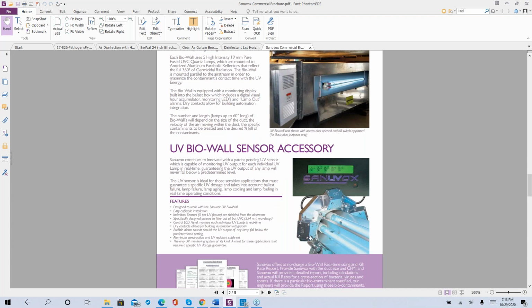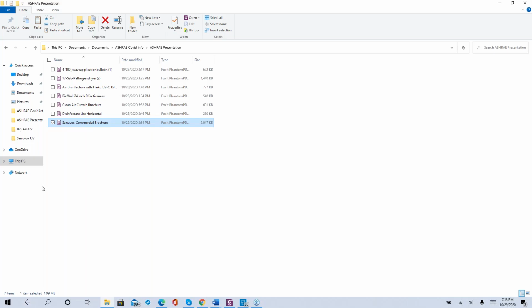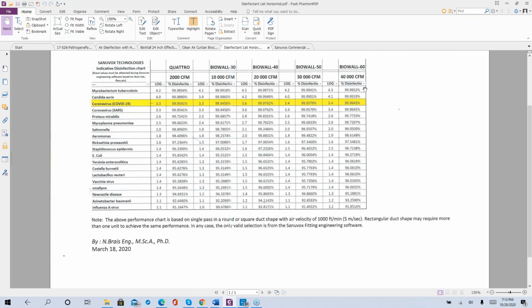And by having it mounted in the middle of the duct like it is, the airflow is going to hit this and roil and tumble. And you can see the reflectors on the other side of the light that is bouncing it off of the aluminum and back and forth. So as long as you have a straight enough section to physically mount whatever the length is in the duct, that dwell time as it rolls across the length of the bulb will give it longer time. That's the reason why they prefer you to mount these in the return air, because typically your return air duct is set at a little bit lower friction and will always be a larger duct.